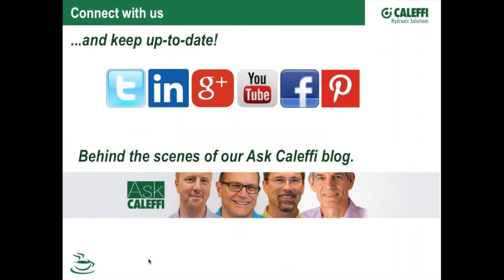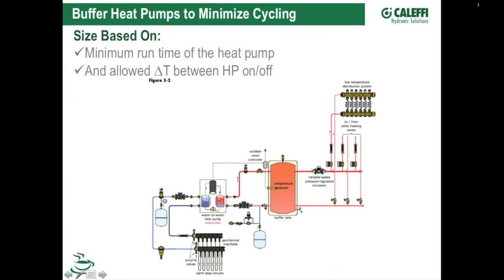Yeah, and that's an excellent question, and that does vary from installer to installer. I know down in Missouri where I live, there's a lot of this going in. The terrain's just right for that, and there's a lot of them that have just regular water in them. As long as you can make sure that you've got this below frost level, that you can get into the basement of a building and you're in a spot where you can use just water, by all means, that's your best heat transfer mechanism.